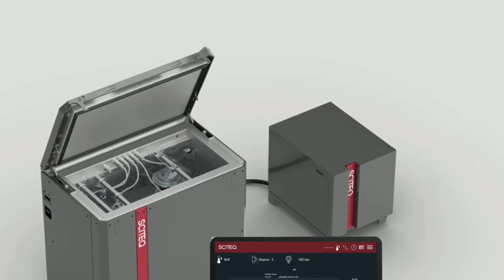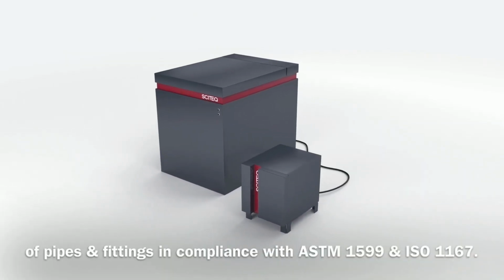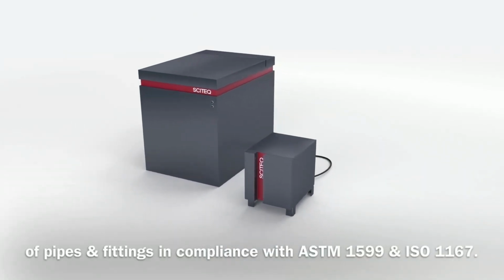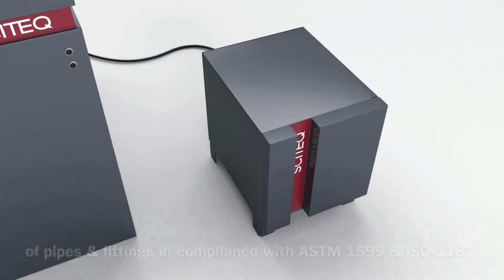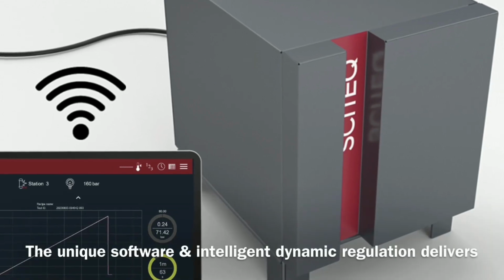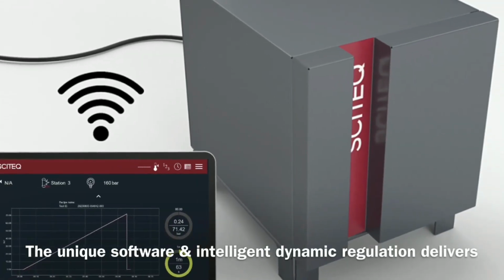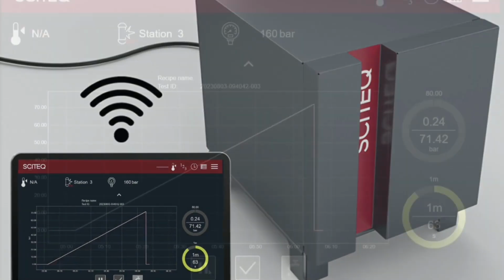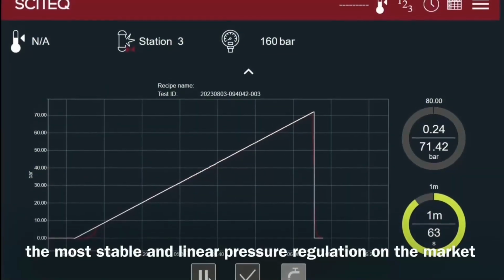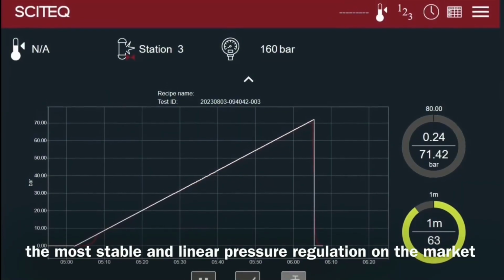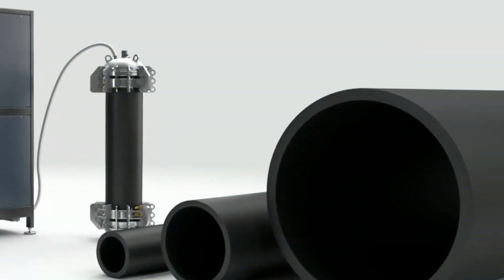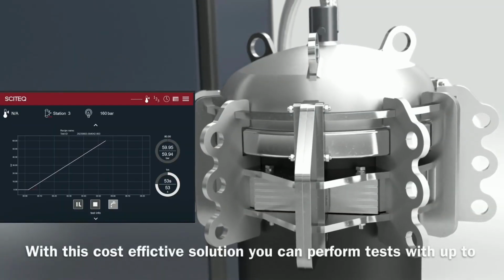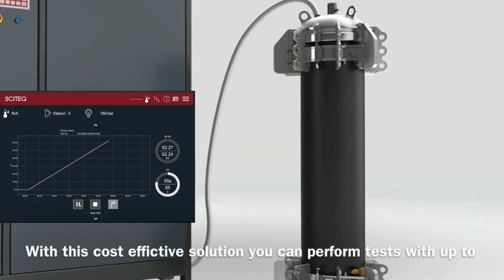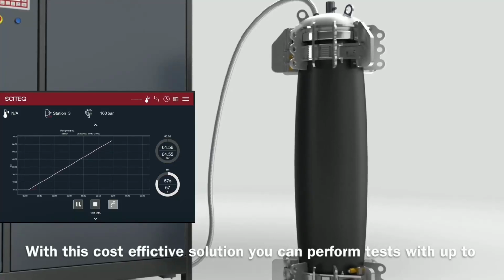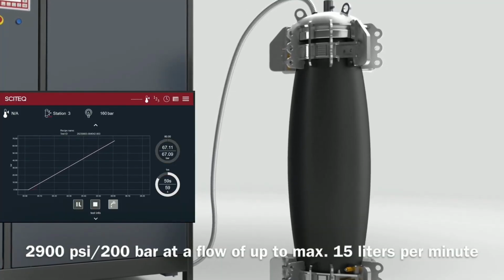burstONE is dedicated for burst and short-term pressure test of pipes and fittings in compliance with ASTM D1599 and ISO 1167. The unique software and intelligent dynamic regulation ensure reliability in a stable and linear pressure regulation. With this cost-effective solution, you can perform tests with up to 200 bars regulated pressure at a flow of up to maximum 15 liters per minute.